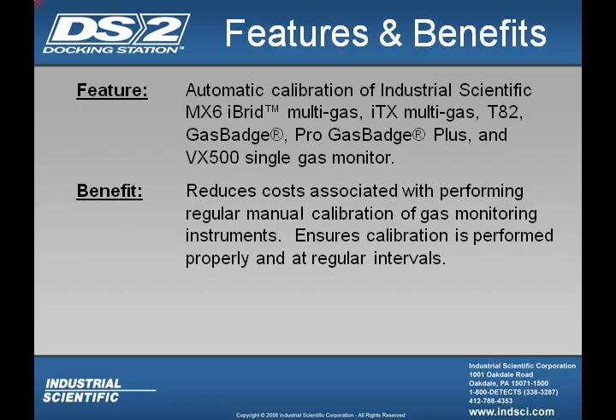One of the features of your docking station is automatic calibration of Industrial Scientific MX6, ITX, T82, Gas Badge Pro and the Gas Badge Plus, and the VX500. Now what this will do is reduce costs associated with performing regular manual calibration of gas monitoring instruments, ensuring calibration is performed properly and at regular intervals.